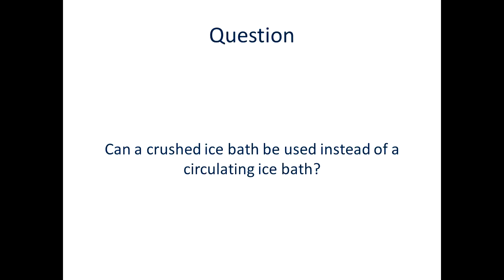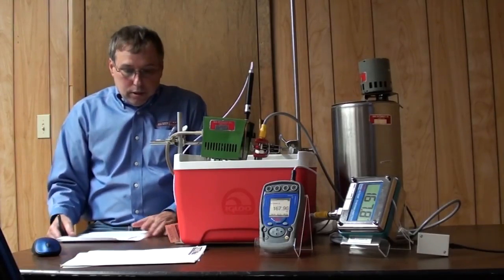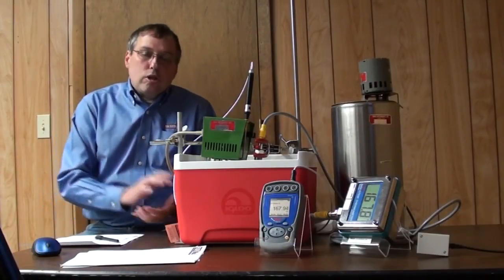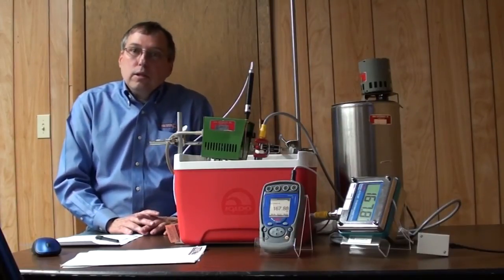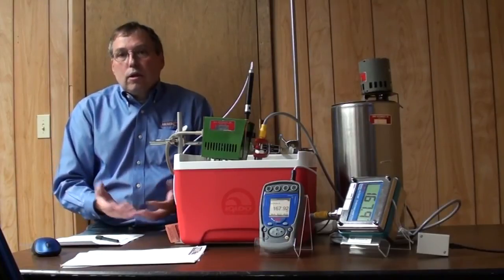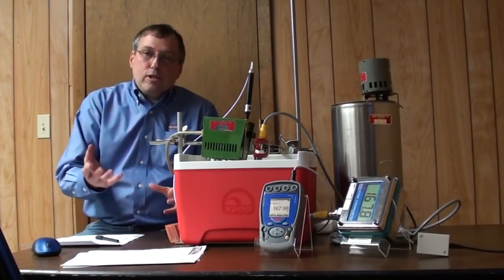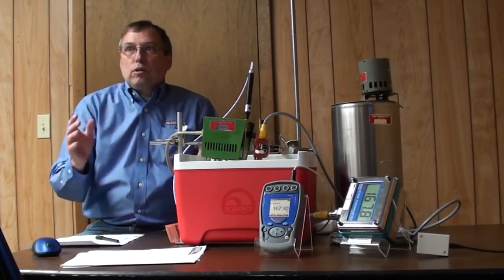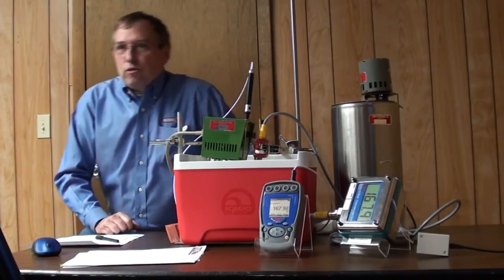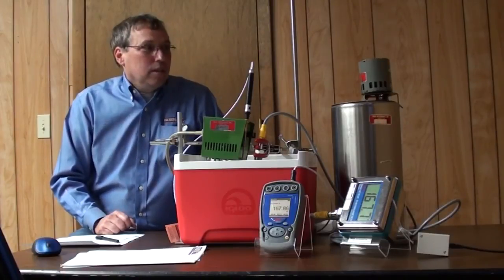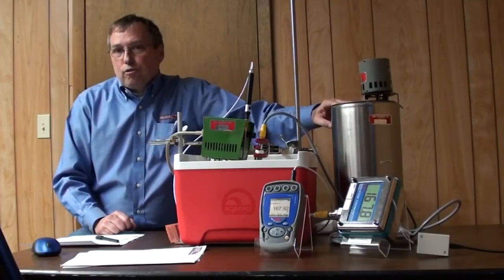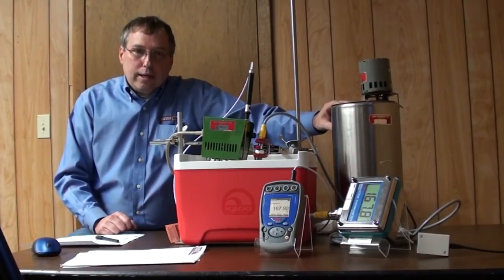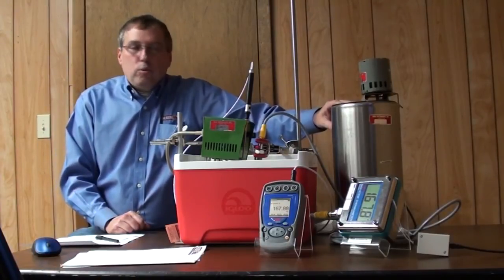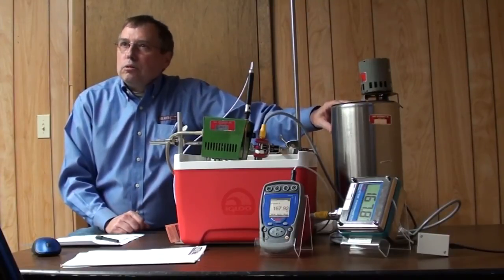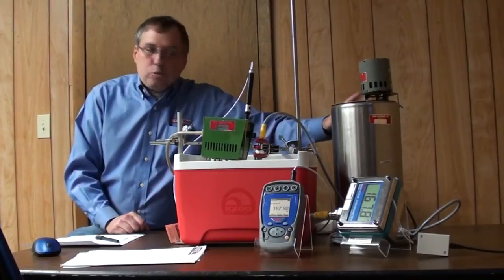Next one. John asks, can a crushed ice bath be used instead of a circulating ice bath? Yes. If you look at the NIST paperwork, if you take crushed ice, now they do specify it should be distilled water that the ice is made from, and distilled water that you fill it with. The reason for that is that if you're using soft water, there's a lot of salt, and I have no idea what the freezing point of soft water is, but it's not 0 degrees C. But honestly, we just use our tap water here. It's fairly clean. We do test these ice baths with an SPRT, and they're usually within 1/100th of a degree or so. 10-15 thousandths of a degree is what we get out of this particular one.